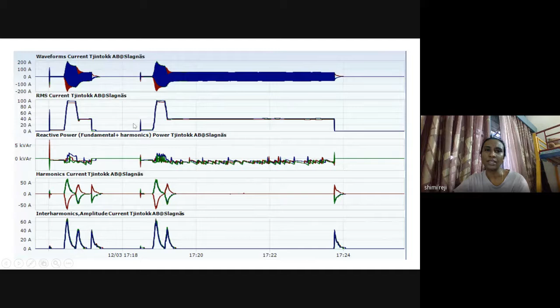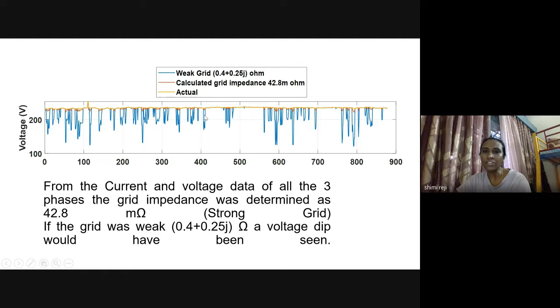These are different patterns, and we tried to find the impedance of the grid. This was a strong grid, so here is the strong grid case, the yellow line and red line being the calculated and the actual one. And we found that if we imagine it was a weak grid instead, you can see large voltage drops like this.